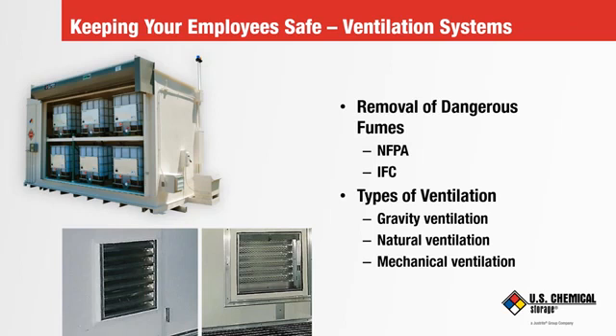If the threat of an explosion is high, and or to avoid installing explosion relief, it is permitted by meeting the requirements of NFPA 69, paragraph 3.3.3, quote, ventilation or air dilution, end quote. Paragraph 3-4.1 adds, quote, suitable instrumentation shall be provided to monitor the control of the concentration of combustible components, unquote. And 3-4.3, quote, alarms shall be provided, end quote.